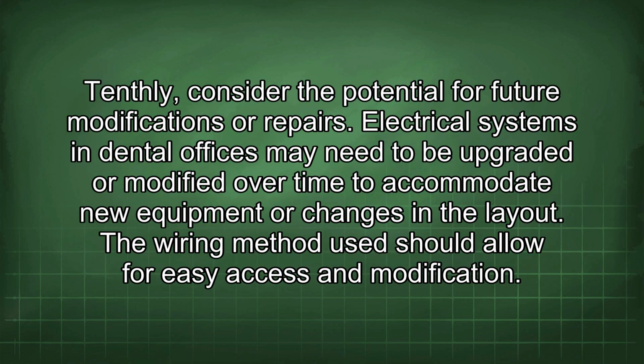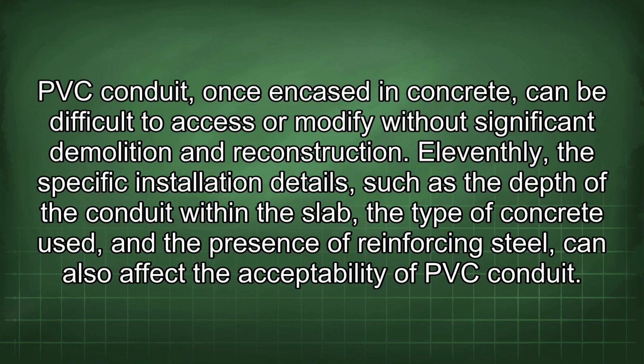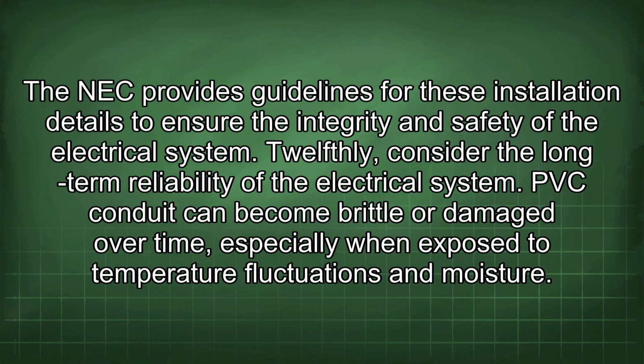Tenthly, consider the potential for future modifications or repairs. Electrical systems in dental offices may need to be upgraded or modified over time to accommodate new equipment or changes in the layout. The wiring method used should allow for easy access and modification. PVC conduit, once encased in concrete, can be difficult to access or modify without significant demolition and reconstruction. Eleventhly, the specific installation details, such as the depth of the conduit within the slab, the type of concrete used, and the presence of reinforcing steel, can also affect the acceptability of PVC conduit. The NEC provides guidelines for these installation details to ensure the integrity and safety of the electrical system.